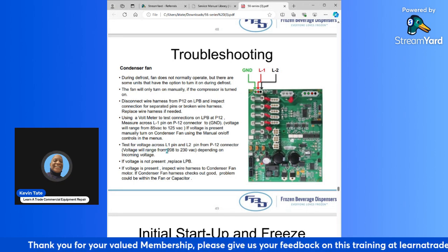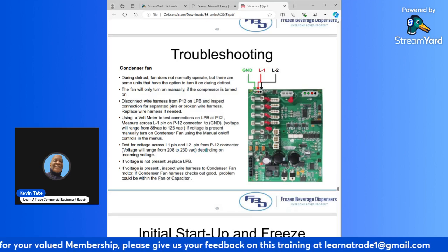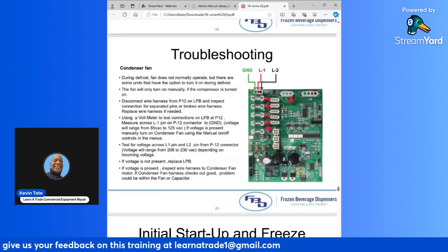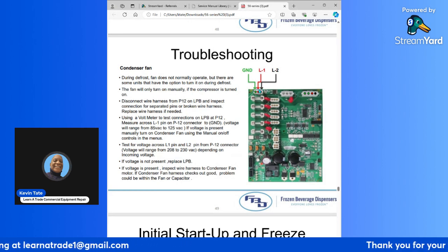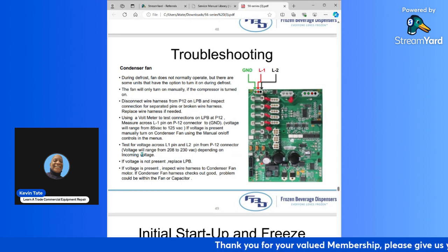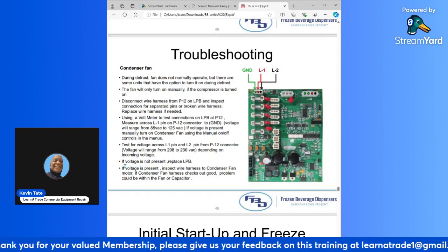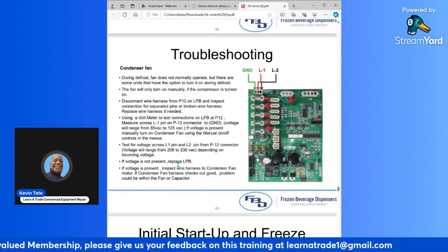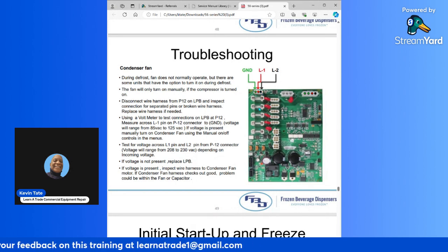Test for voltage across L1 and L2 pins from the P12 connector. So this one you're going to test across L1 and L2. The voltage ranges from 208 to 230 volts AC, depending on the incoming voltage. If voltage is not present, replace the lower board. So if you do not have power there, then you want to replace the board.